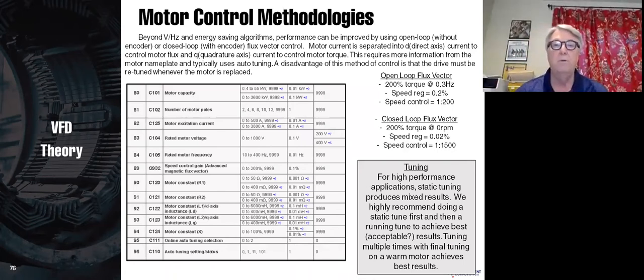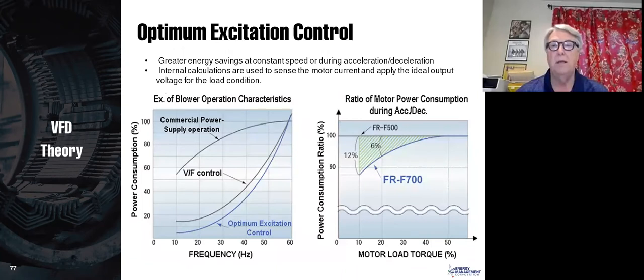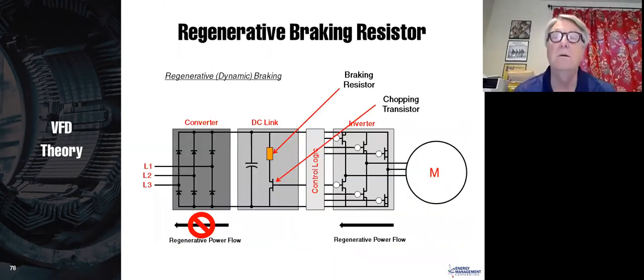If you have open loop flux vector and you want to use it, then it requires that you actually tune the motor, and we may get into that later. Optimum excitation control actually looks at the load on the motor and adjusts the volts per hertz accordingly. So if you don't need full torque, it will actually reduce the volts per hertz, which saves you a little bit of energy, not a lot, but it also tends to decrease vibration. So that's a feature of a lot of advanced drives.